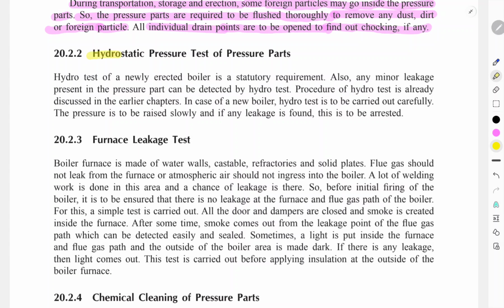Now the next one is the hydro test, the pressure test of the parts. The hydro test of the newly erected boiler is a statutory requirement, a very important requirement. Also, any major leakages present in the pressure parts can be detected by the hydro test. The procedure of the hydro test is already discussed in an earlier chapter. In the case of a new boiler, the hydro test is carried out carefully. The pressure is raised slowly, and if any leakage is found, it is to be arrested. Okay, the hydro test should be done. Furnace leakage test, very important. Furnace leakage test.